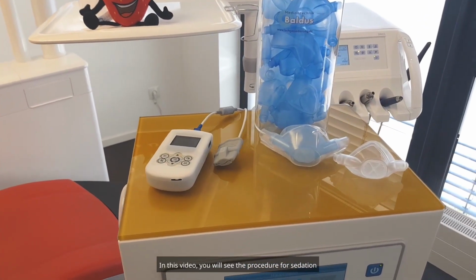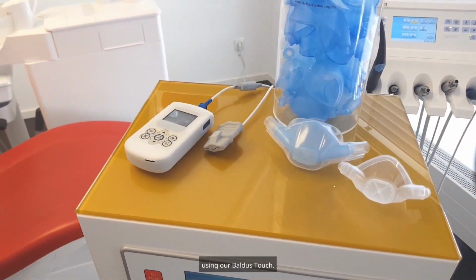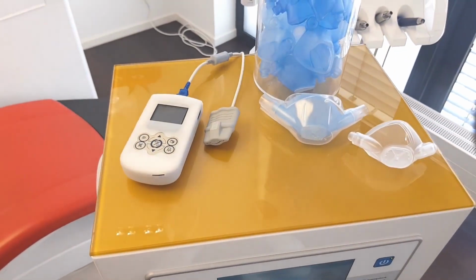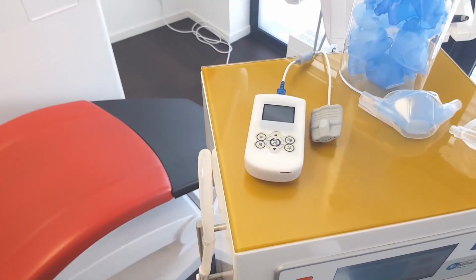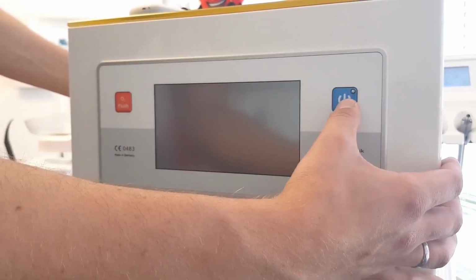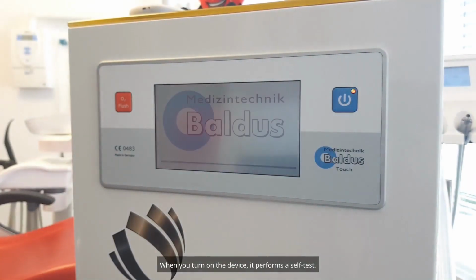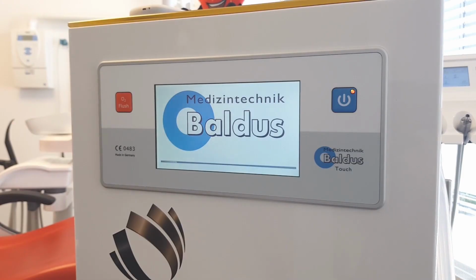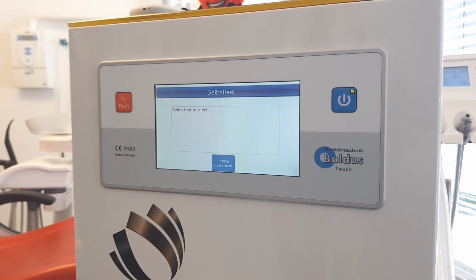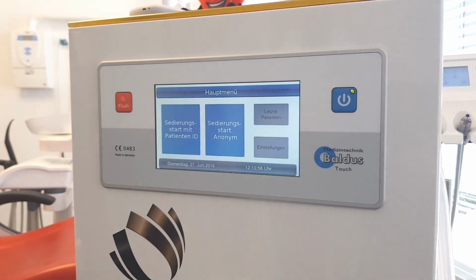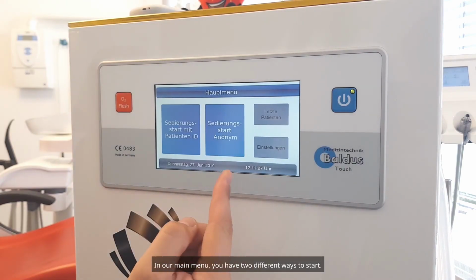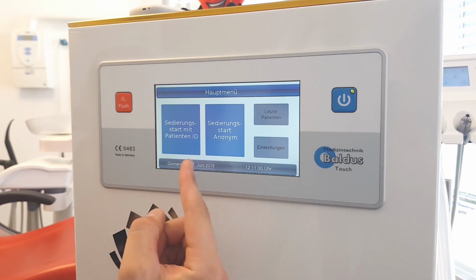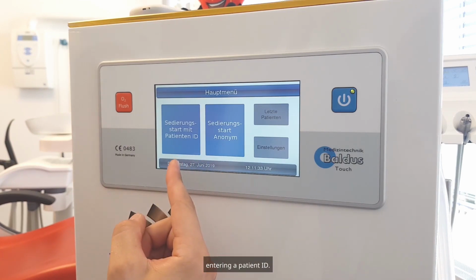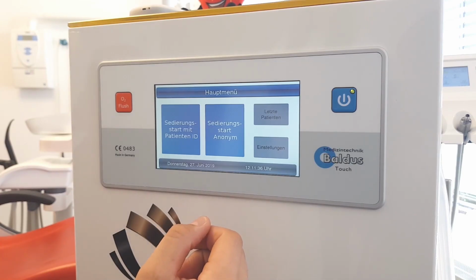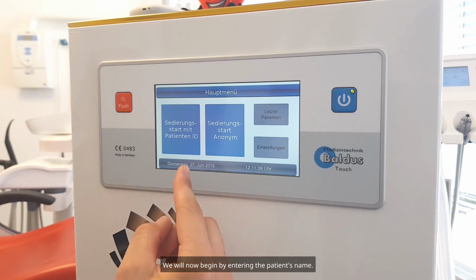In this video, you will see the procedure for sedation using our Baldus Touch. When you turn on the device, it performs a self-test. In our main menu, you have two different ways to start. You can either start the sedation anonymously or by entering a patient ID.